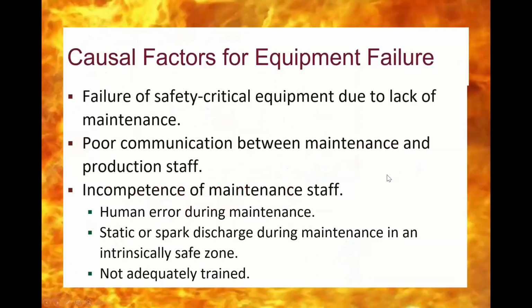So some factors to consider on failure. So some of the things are due to lack of maintenance, and including the lack of maintenance includes short circuit and ground and the coordination studies. Communications, human errors sometimes will cause the actual fault itself. It can be during maintenance, it can be other times, but a lot of times during maintenance. Sometimes static or other types of discharges, or fumes and dust and things like that. And sometimes people just aren't trained to know what's going on.